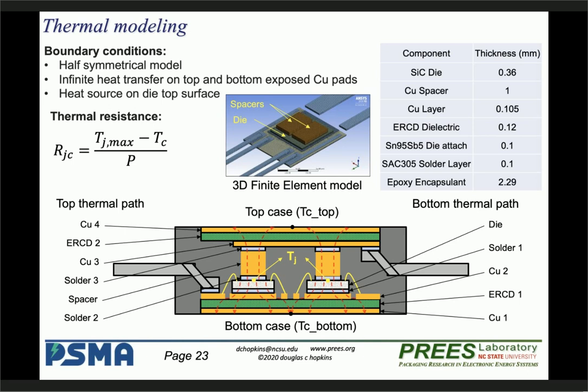Layer thicknesses of dielectrics, and also positioning of different dielectric materials within the structure to do field warping, to optimize the voltage profiles on highly stressed dielectric areas. For instance, if you're using a silicone gel, you have to make sure your dielectric stress at high field intensity points is managed so you don't have localized breakdown and degradation over time of your encapsulates. We're just starting to publish in this area, with a transactions paper in draft that I'm reviewing. It's very interesting to look at multi-permittivity materials at critical places within the structures to get electric field morphing.